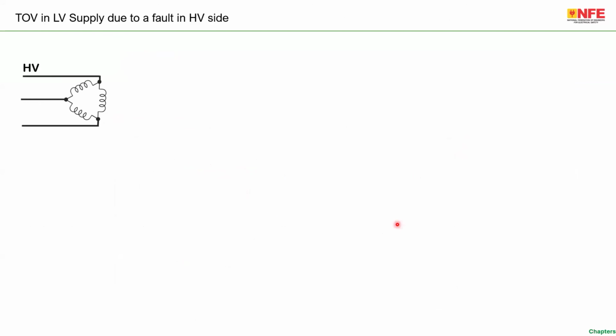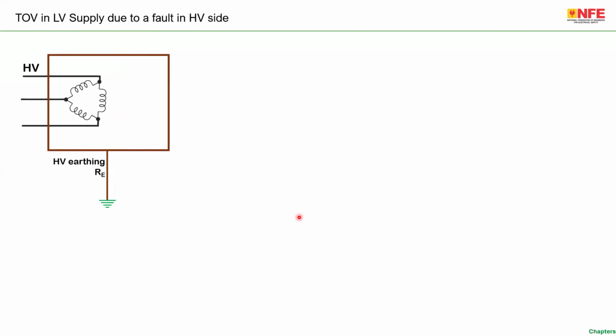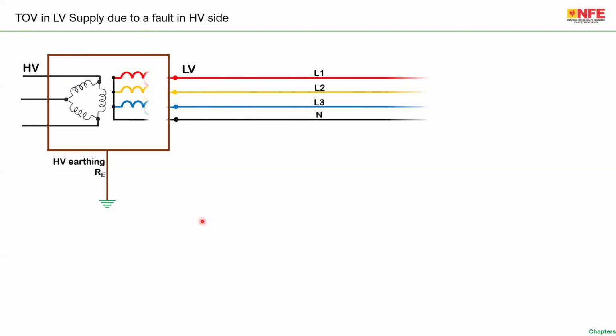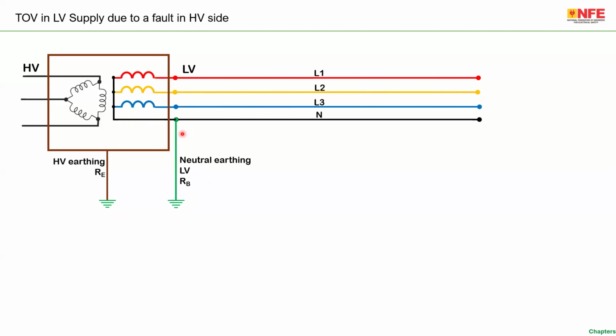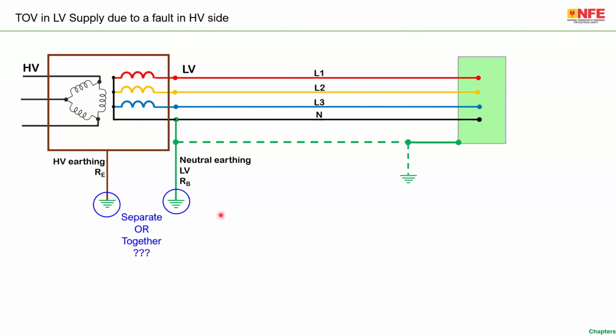For example, you have a high voltage transformer. The brown color line is the transformer HT earthing, let's say high voltage earthing, which is RE. RE is the earth electrode resistance. You have the low voltage winding of the transformer. Imagine the low voltage neutral is also earthed or connected to the reference point. The question you will always be asking is whether RE and RB, the HT and LT sides, are together or separate.